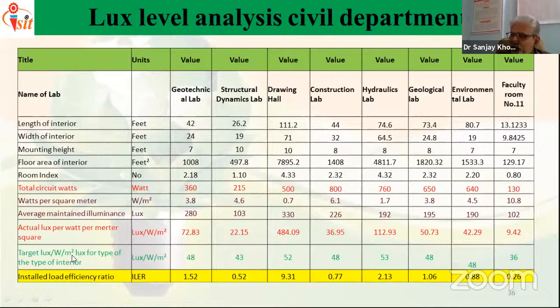But as per the standards, how much should it be? The target lux per watt per meter square for this particular type is 48. That means in that laboratory, they have unnecessarily installed more tube lights than needed. So this installed load efficiency ratio, ILER, is very important. It should be up to 1, and 0.75 to 1 is the best, excellent or good range.